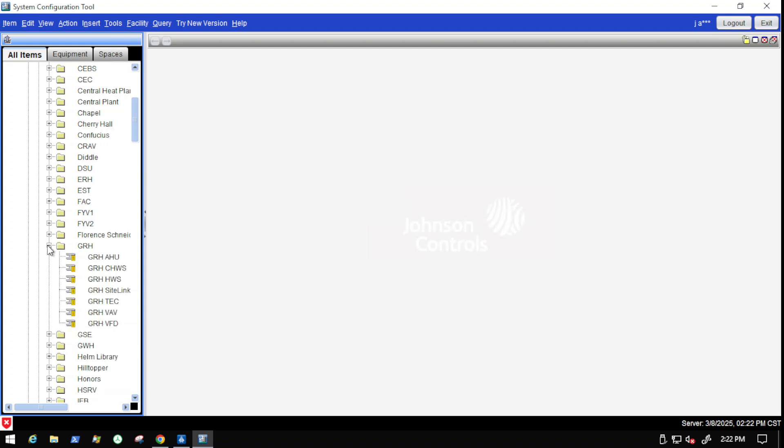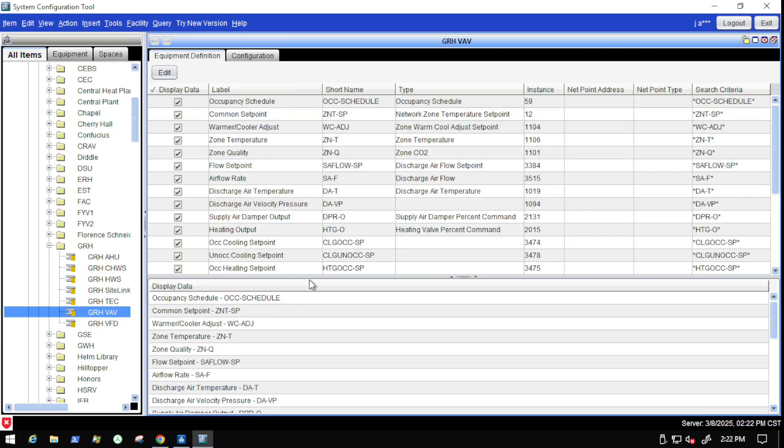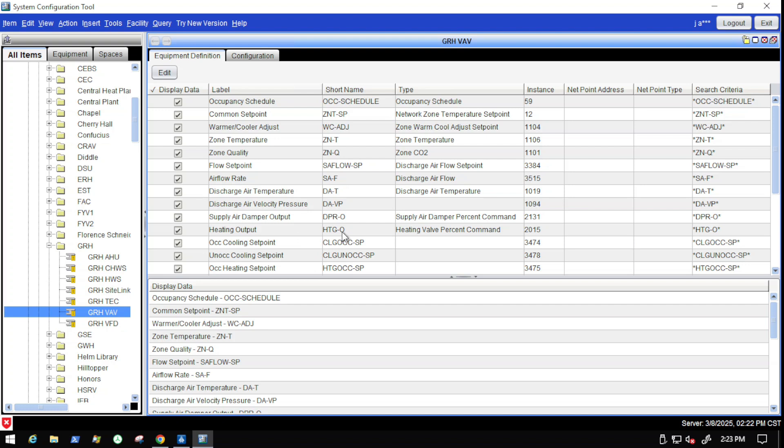So what we're going to do here is we're going to drop down the equipment definition folder containing the one that we're looking at on screen. When you go in here, I'm just going to double click the equipment definition first and show you the summary of all of the points. You can see here what I want to do when I set one of these up. I want to set it up to include everything that could potentially be in one of those VAVs. So I'm going to base that on a VAV that has the majority points. For example, this one is based on a VAV that does have the heating output.